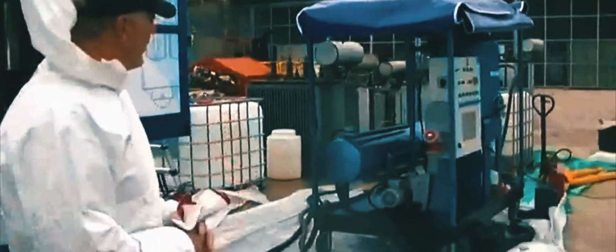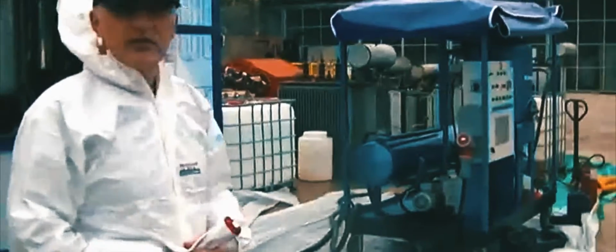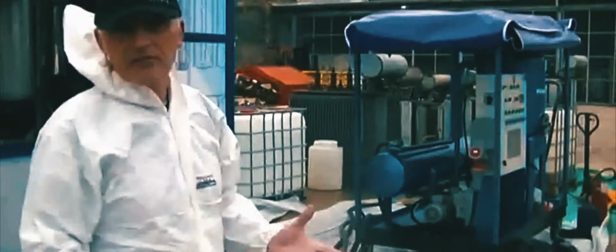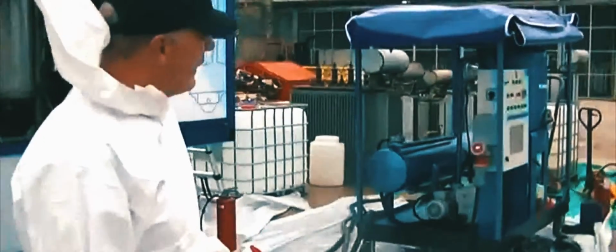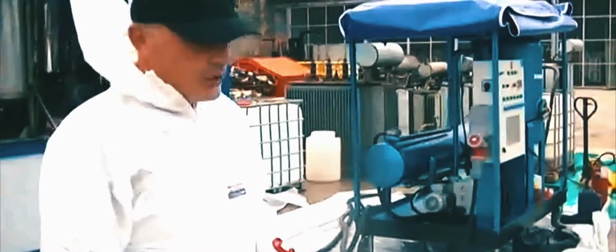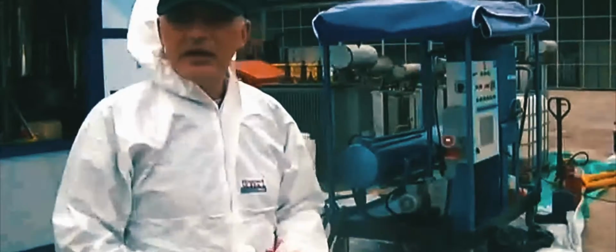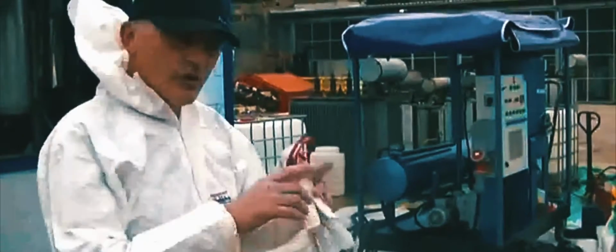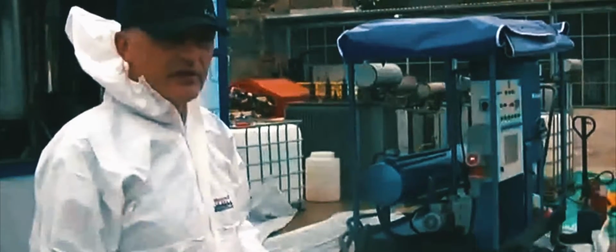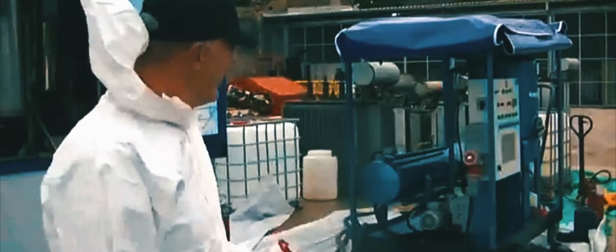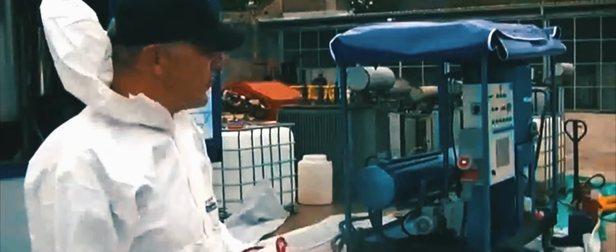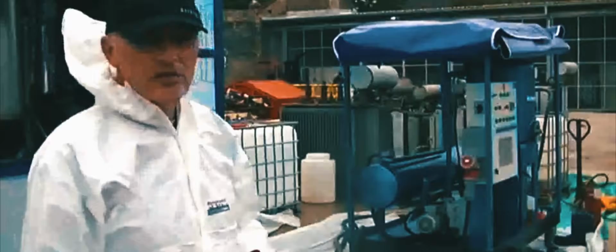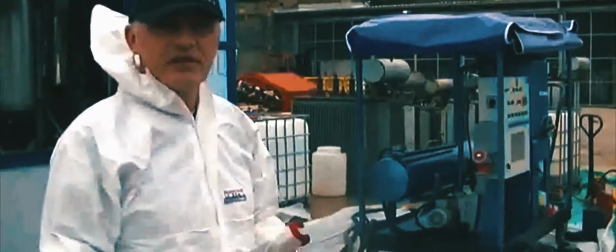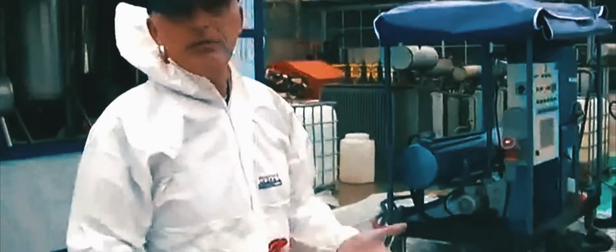After that section, the oil can be returned safely to transformers and used again. When we fill the transformers once more with this oil - I was showing you that red label saying the equipment is PCB contaminated - once we remove this PCB contamination, we can put a white label saying the equipment is PCB free.